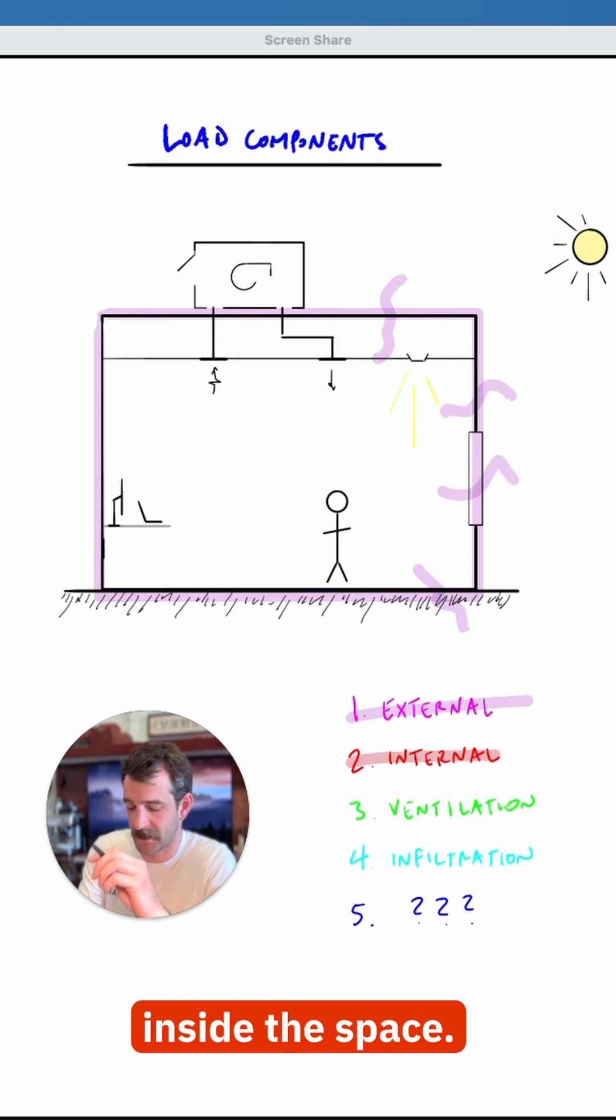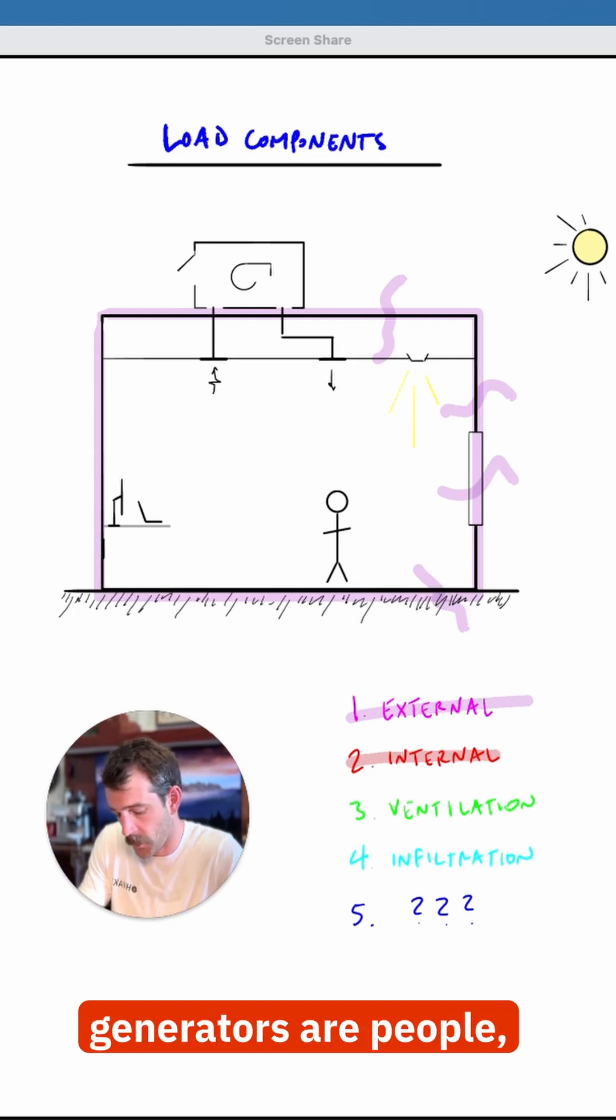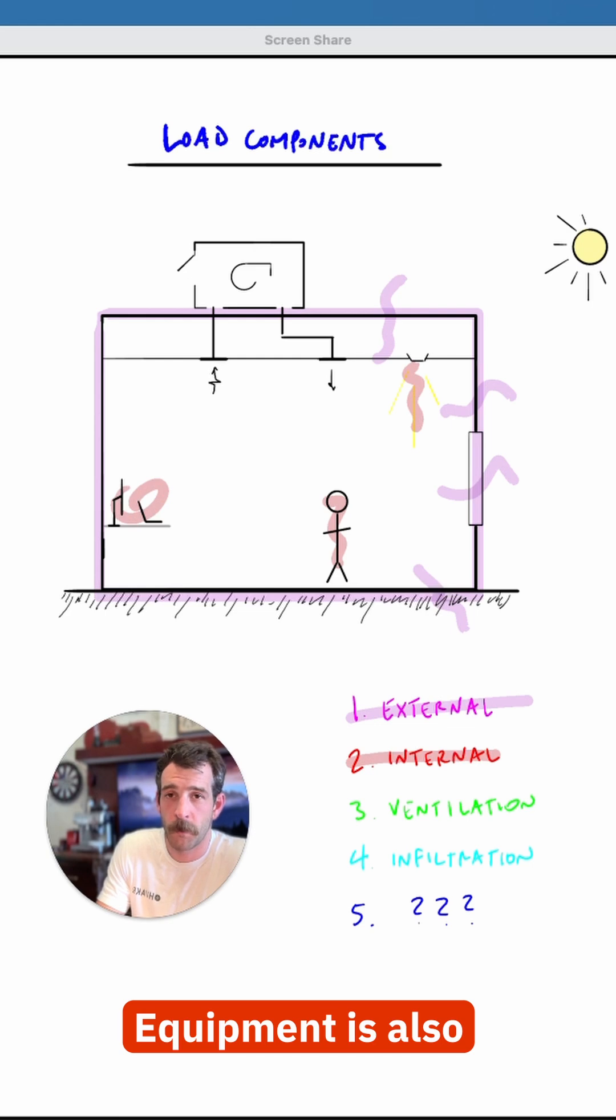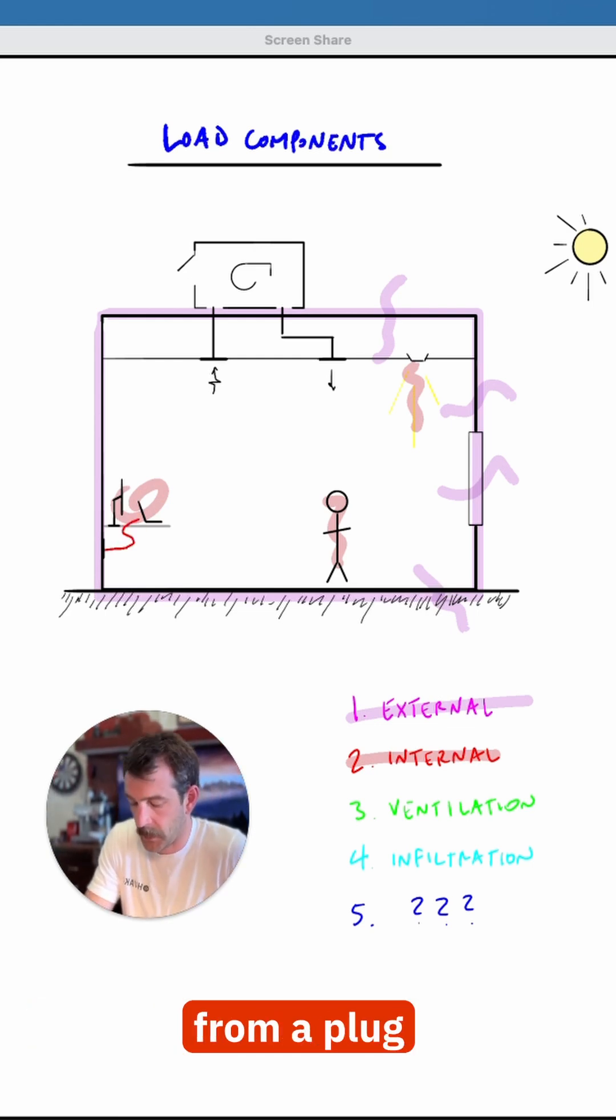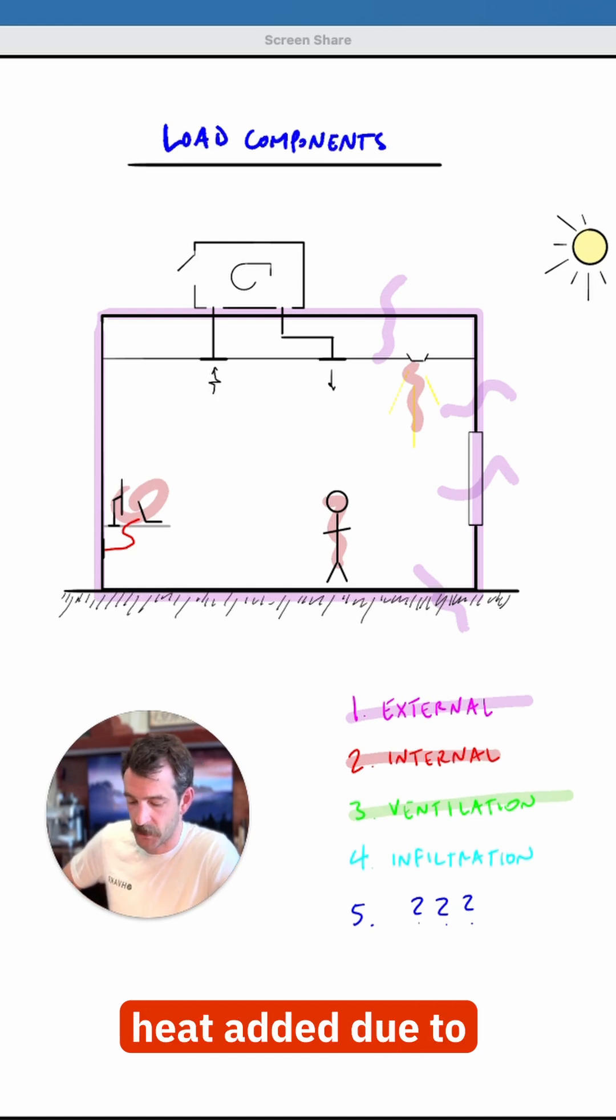Number two is internal. This includes any heat that is being generated inside the space. The most common generators are people, lights, and equipment. Equipment is also called plug load because the heat generated ultimately comes from a plug.